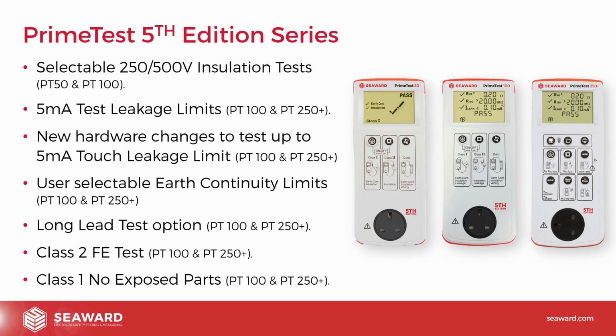Long lead option. So historically, again, having a set pass-fail limit was always difficult because if you've got a long lead, then potentially you test a long extension lead and it fails because it's over the preset limit. So now we've added in a function where it'll actually come up and ask you, is it a long lead? And then you can carry on and do the test, and it will test that and give you a value for those. So again, that's been added to the Prime Test 100 and the 250 Plus.